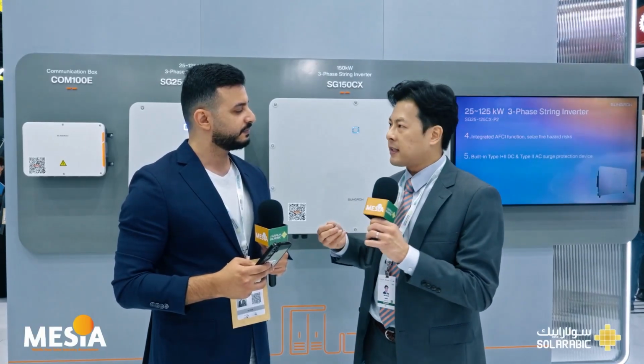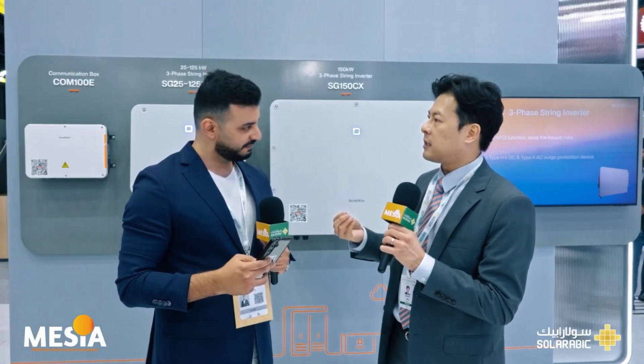It can provide a response within 5 milliseconds during the startup of the black start, when the power is actually from zero, right? This fast response from the synchronous generator can provide inertia immediately wherever there is any step change in the system. So when you're ramping up the voltage, you can very reliably address these frequency issues and also the inertia issue from this black start, which is offered by the grid forming technology.